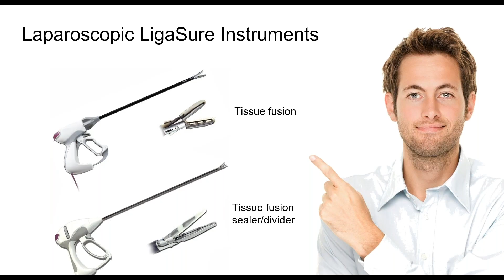When we seal a vessel, it's a combination of pressure, energy, and time. That's what seals it. The pressure is all predetermined too. When you put that across the vessel and you click it shut, you can let go of it. It's all predetermined. That means you couldn't put more pressure than that. It's the way it is, okay? And then energy: you would either hit the button on the back of the instrument or use the foot pedal on the floor. It would seal that with heat; the energy would produce heat. And then the last part of this is time. Depending on how thick the tissue is that they were putting this across, it would take longer. But what they would always wait for is, does anybody know? What are they waiting for?